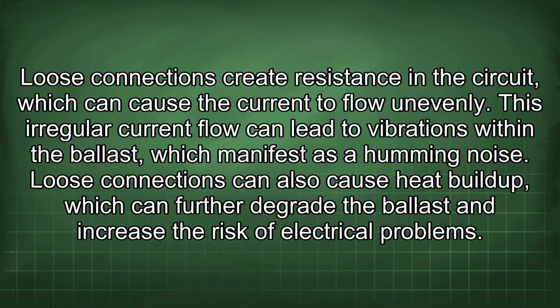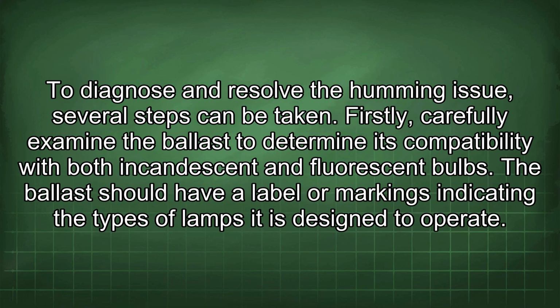This irregular current flow can lead to vibrations within the ballast, which manifest as a humming noise. Loose connections can also cause heat buildup, which can further degrade the ballast and increase the risk of electrical problems. To diagnose and resolve the humming issue, several steps can be taken.